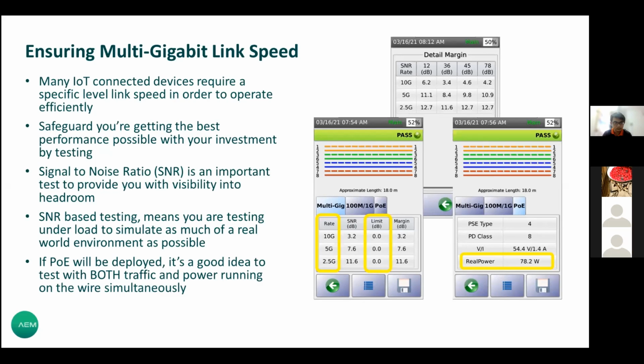If you have an intermittent problem, this parameter will help you indicate where the issue is. If you run a higher data rate, let's say you go straight to 10 gig, it is more sensitive. If there's a slight noise, the signal will be affected. You can see in this slide I have 3 parameters, all based on copper: 2.5, 5, and 10. At 2.5, I got 11 dB, because this is a slightly lower data rate, so the margin is higher. But when you go higher to 10 gig, your margin becomes 3.2. Data centers now are running on 10 gig. So this important measurement allows you to indicate whether your signal is good.